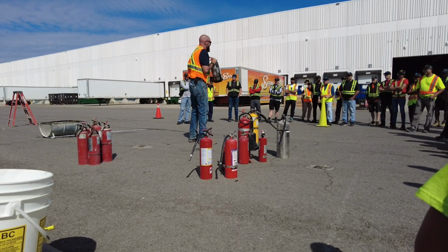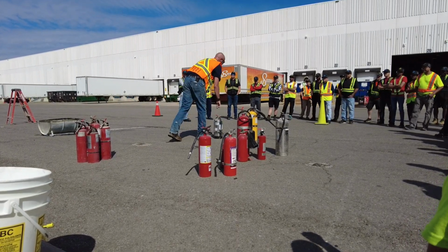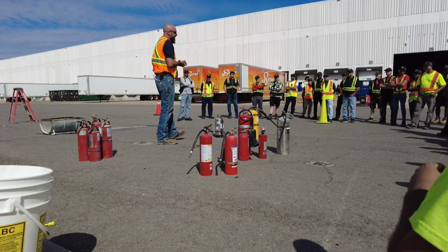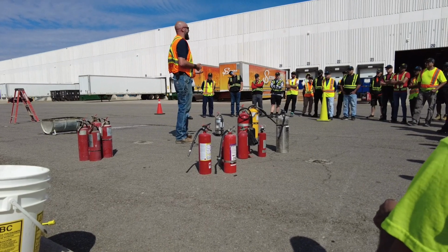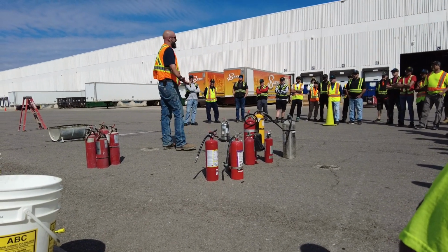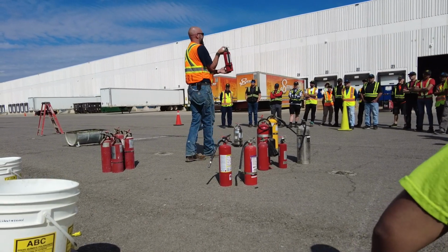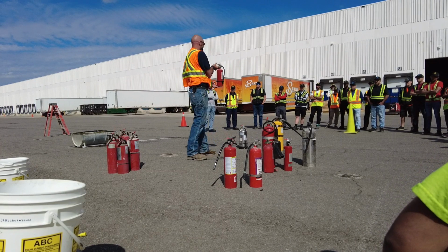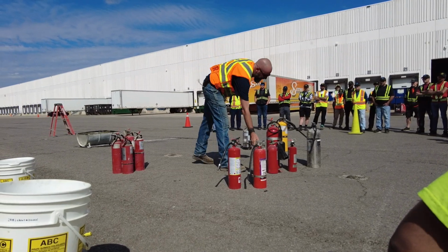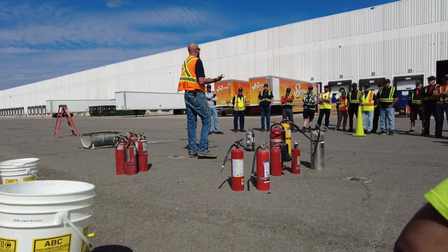No. This was designed because back in 2000-ish, just after I started, everybody started switching from using fat and lard in their deep fryers to high temperature cooking oils. So, we used to be able to sell you this to cover your deep fryer and all your kitchen equipment. High temperature cooking oils changed that. The powder won't keep the fire suppressed and it will reignite.